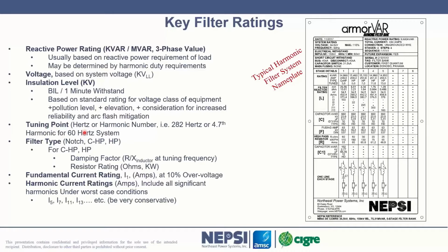Tuning point is another key parameter. What are the tuning points of the harmonic filter? Oftentimes we might say we have a 4.7 tuned harmonic filter, that's equal to a 282 hertz tuning point. So we take 60, in this case this is based upon a 60 hertz system, 60 times 4.7, I get 282 hertz. So that's where that comes from.